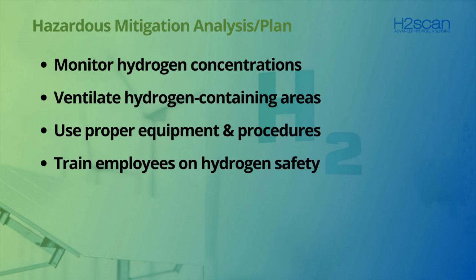So with applications that contain hydrogen, the codes and standards encourage us to create hazardous mitigation analysis to feed into our hazardous mitigation plans. So I created a few bullet points that outline some of the safety items that we need to consider for our hazardous mitigation analysis. The first one is monitoring hydrogen concentrations. And so we should know exactly what our concentrations are, if it has to do with normal operation or looking for leaks or monitoring safe levels within a specific space or room.